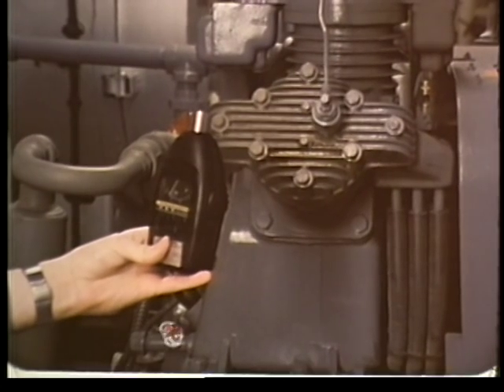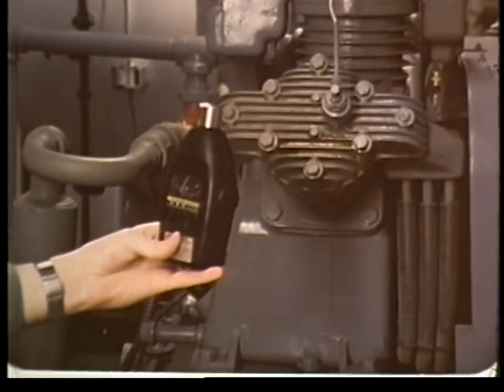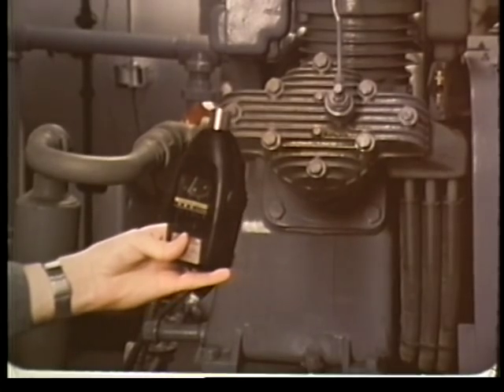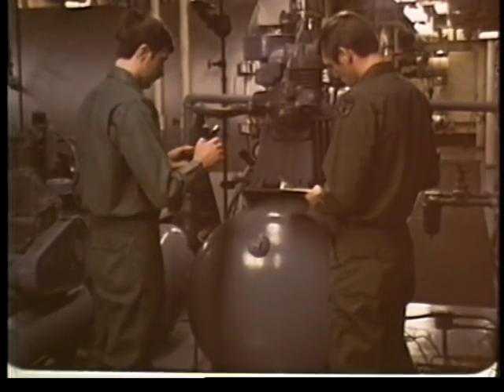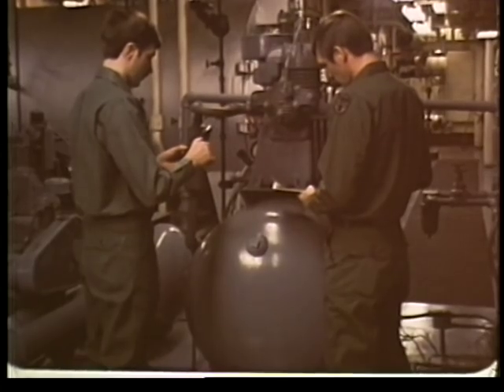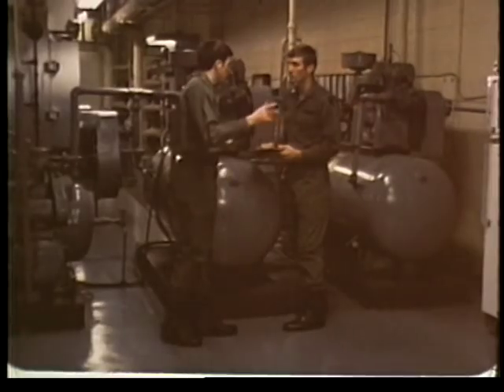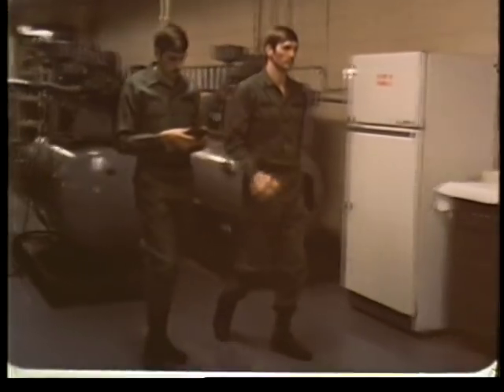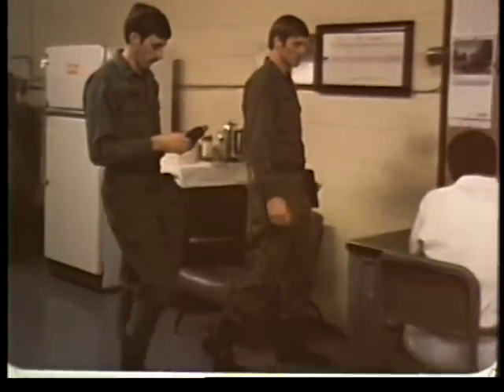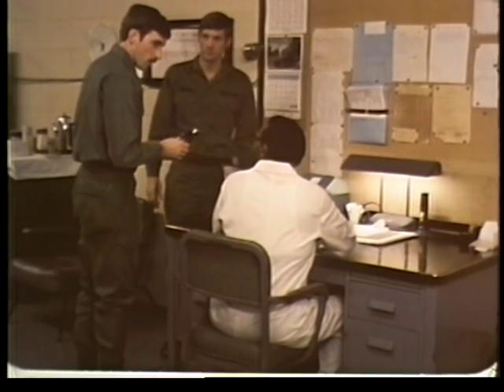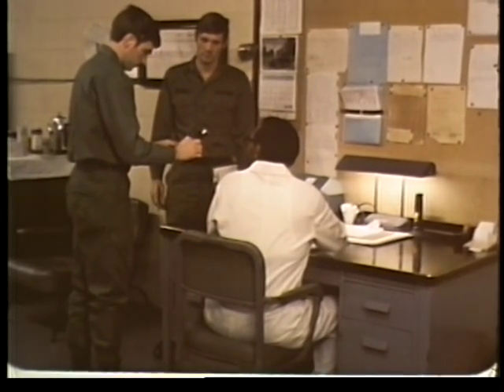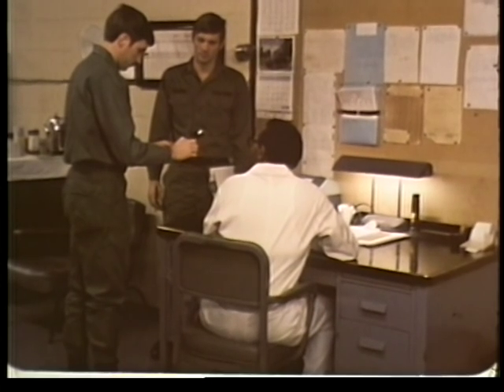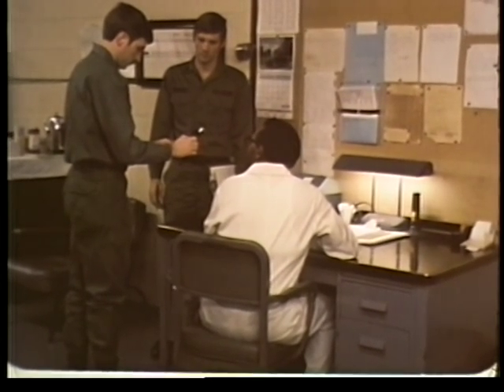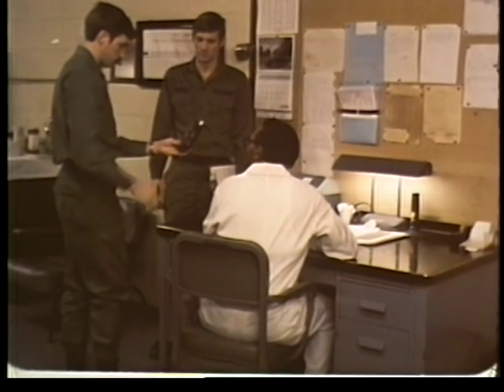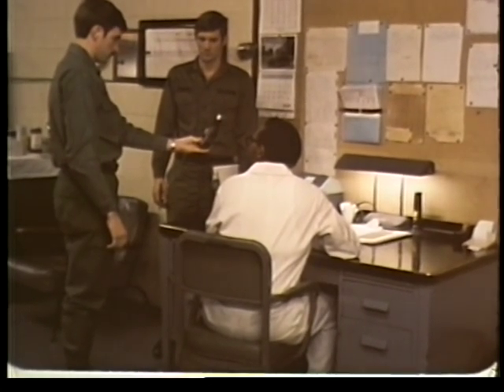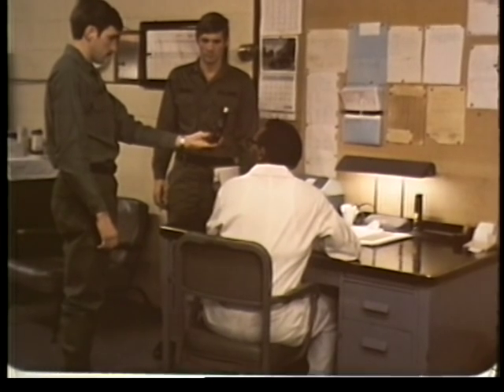Notice that you hold the meter so that the microphone does not point toward the noise source, but instead points at right angles to it. Make sure you take a reading at any area where the worker spends a lot of his time. Take the reading close to the worker so that you measure the noise as he actually hears it. Position the meter so that it is between the worker and the noise source, and so that it is not being blocked by your body or the worker's.